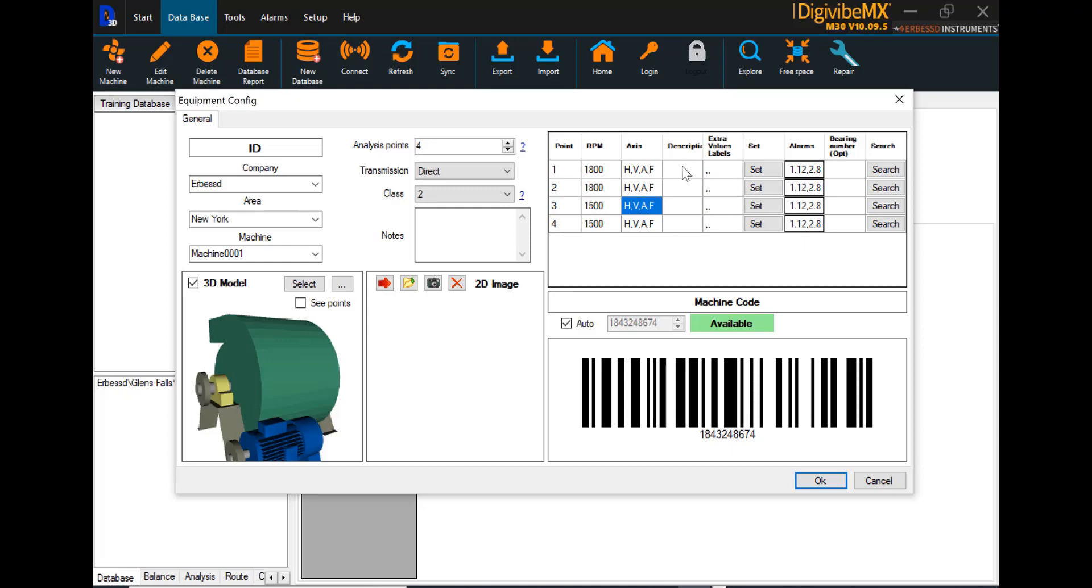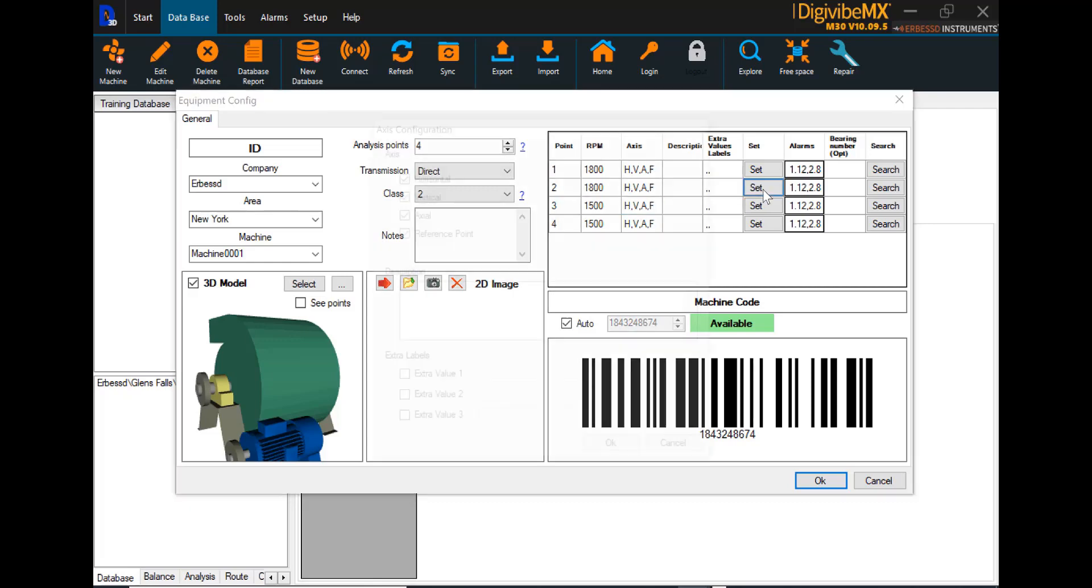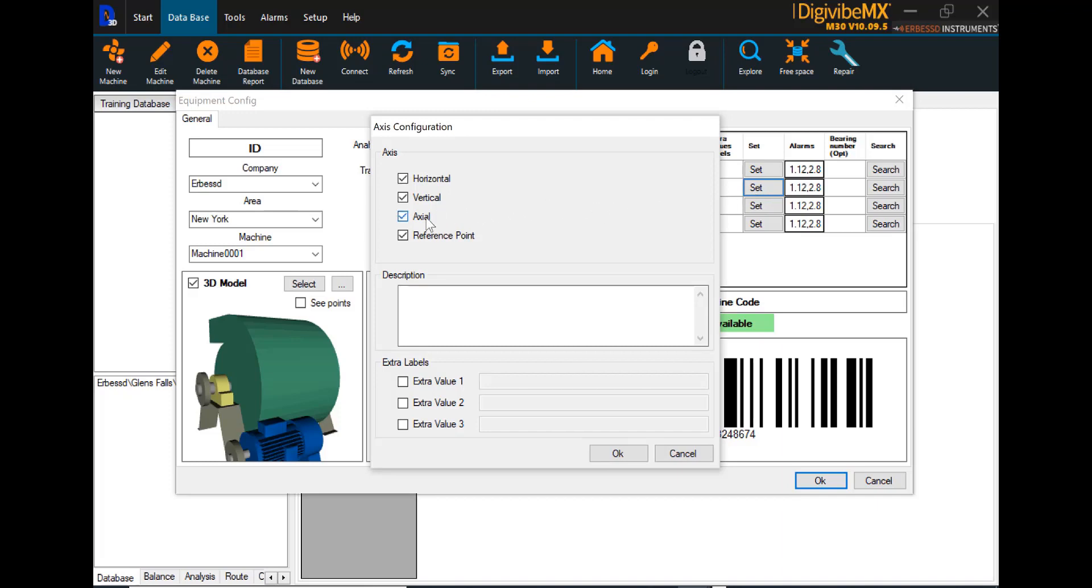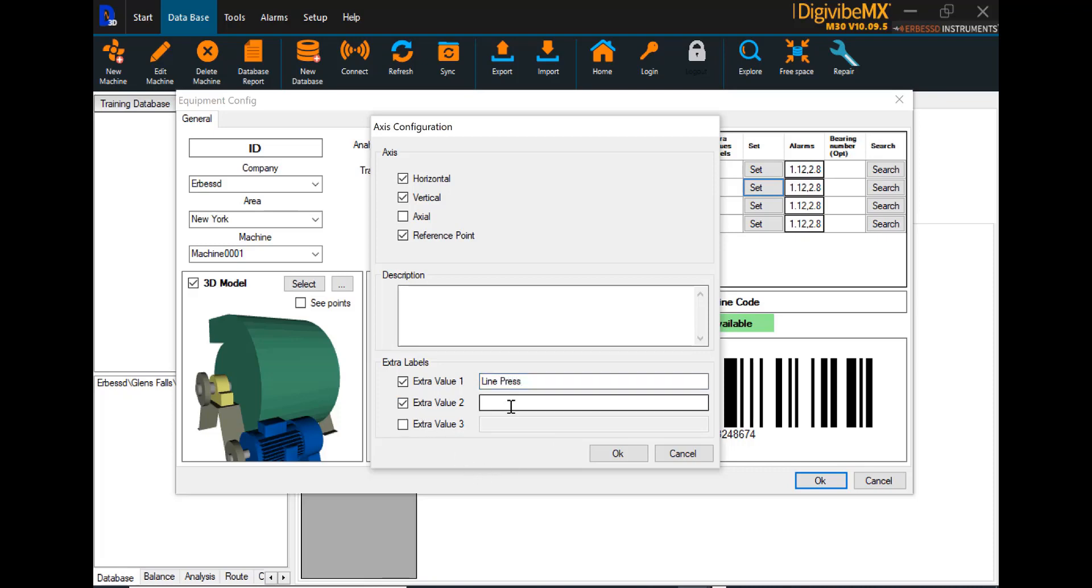There's additional information we can assign. We see here that, by default, all four axes are loaded for ODS collection: horizontal, vertical, axial, and the reference point. If we do want to change or remove some of these points, for example, most data collectors do not collect axial in both directions on a piece of equipment. They'll collect one or the other. We can open the point we want to remove a collection from, simply uncheck it. And if there are any other additional values that we would like to manually enter while we are on the route, we can assign those here under extra value labels, things such as line pressure, and select OK to save those.